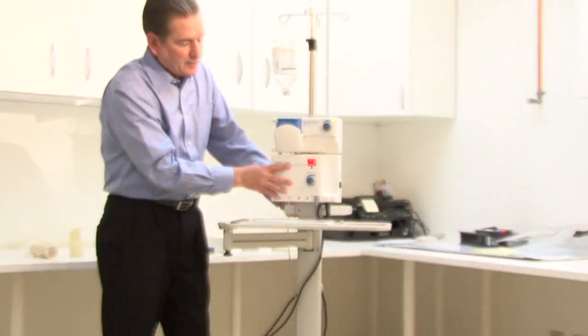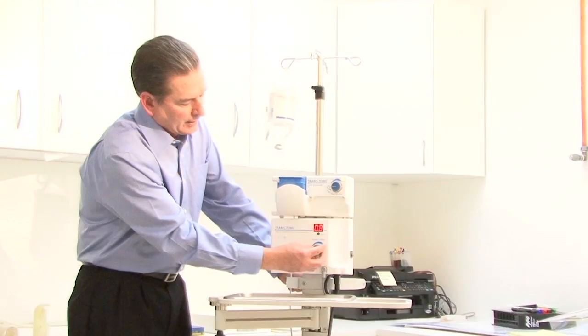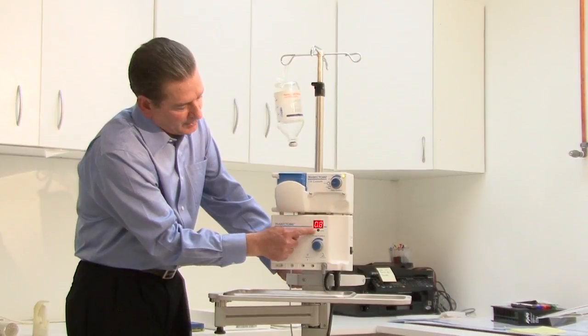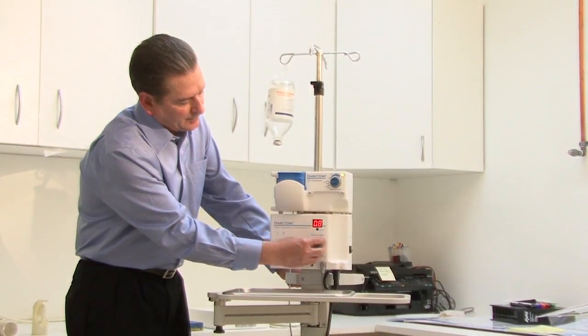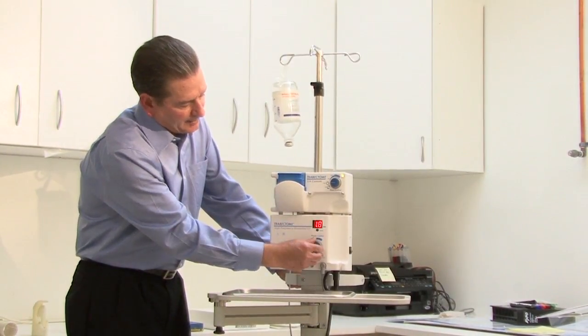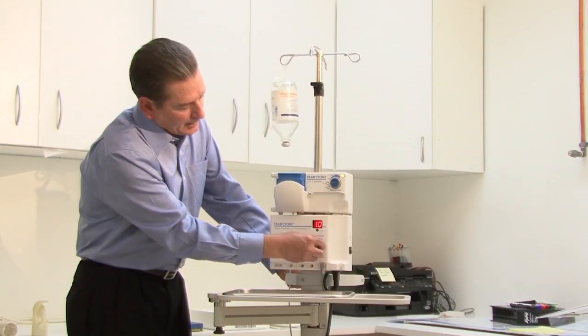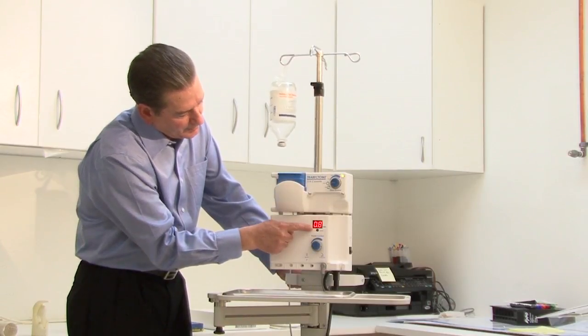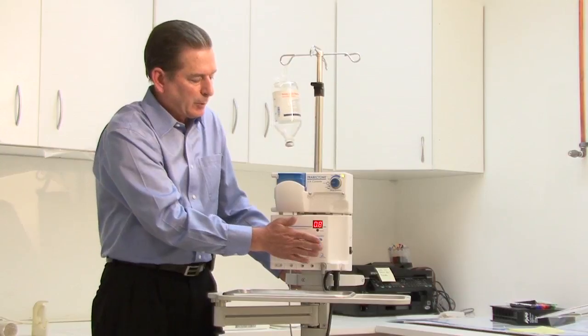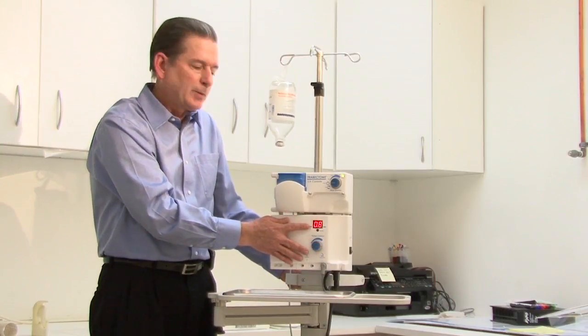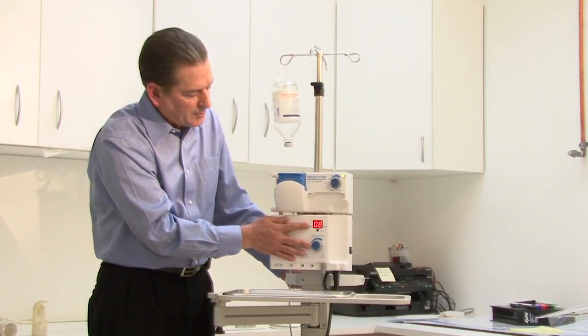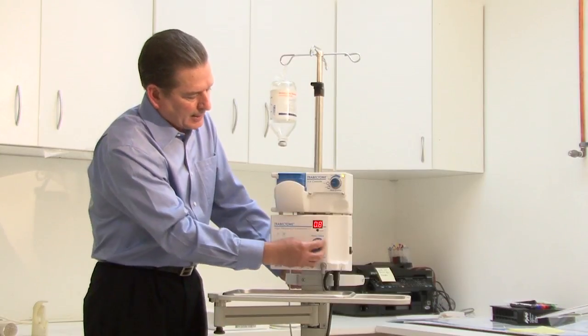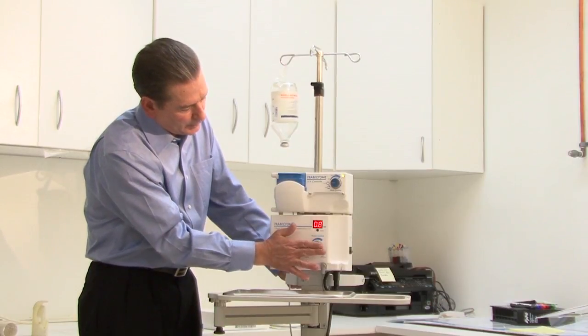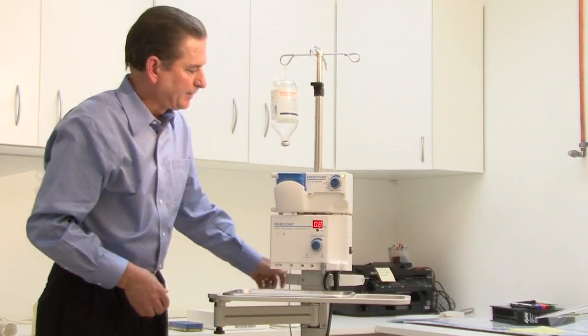And on the generator, there's really only one control. It's just the adjustment of the output power that's delivered from the generator, and that's just adjusted here with the knob. And you'll see that the adjustment to 0.8 watts is where we're going to leave the generator. That's the most typical setting for trabectome surgery. So it's a very low power procedure, and that's simply adjusted here with the knob on the generator.